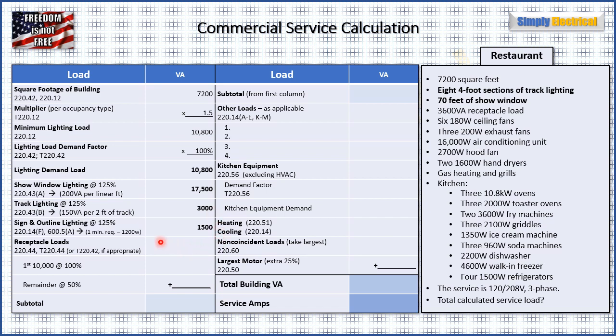Next, sign and outline lighting. We don't have anything in our data specifying signs, but per 600.5A any commercial building must have at least one circuit for every entrance used by the public. We're going to assume just one entrance since we weren't told differently, so we put our one minimum requirement. Per 220.14F, that's 1,200 watts for that circuit. Multiplying 1,200 times 125% gives us 1,500 VA.